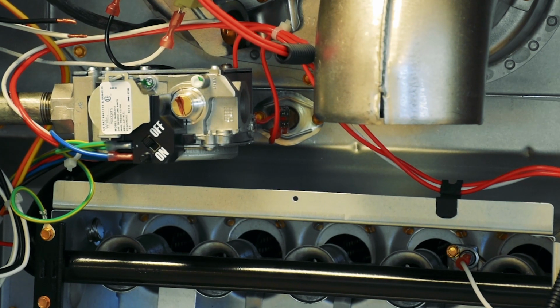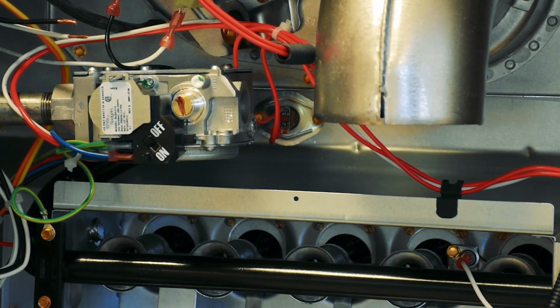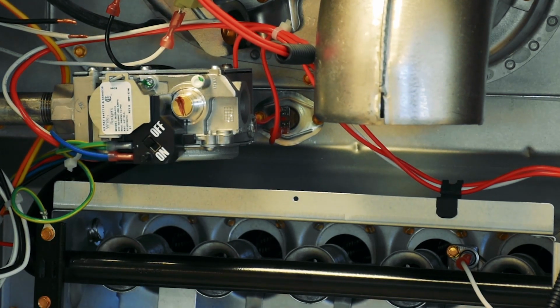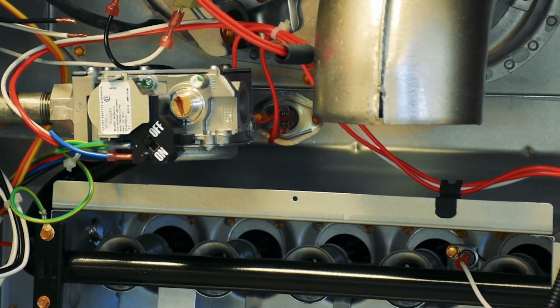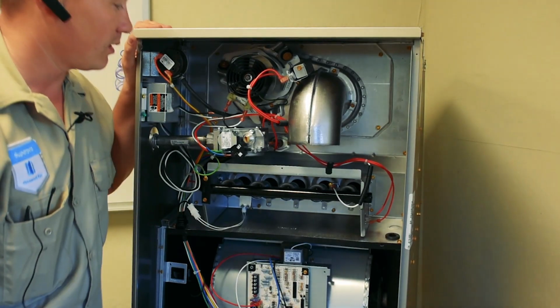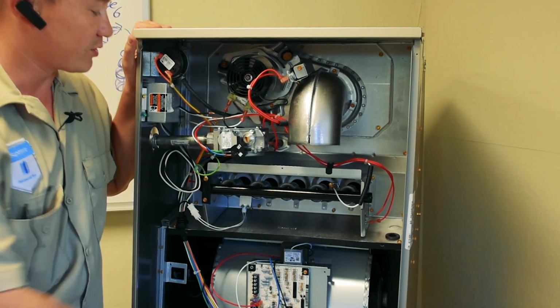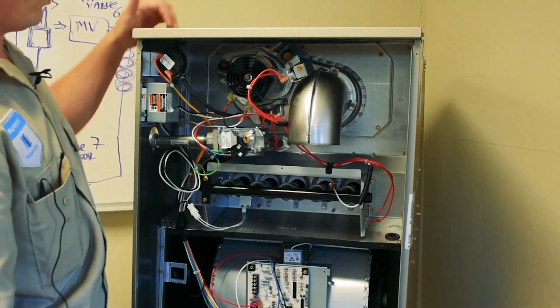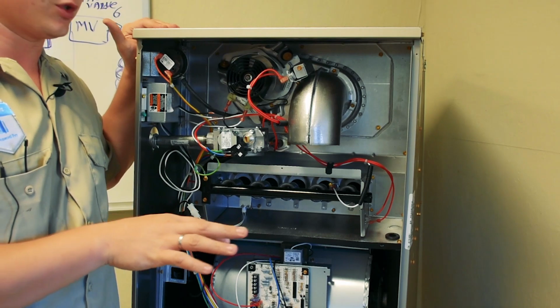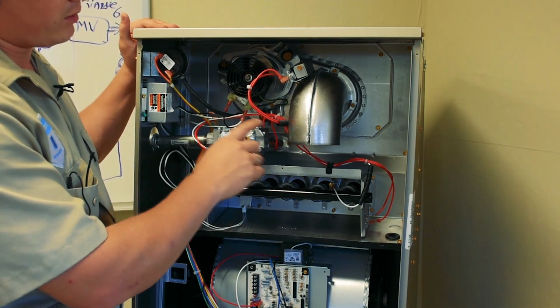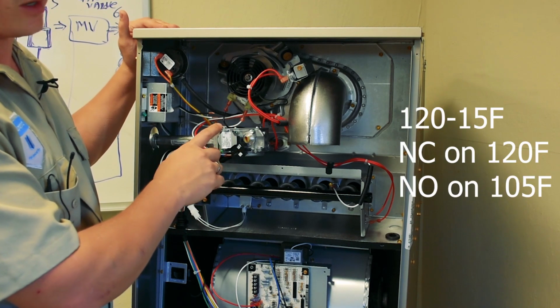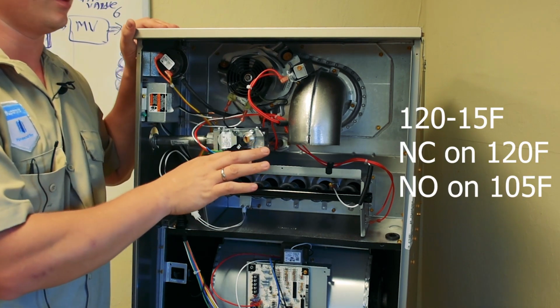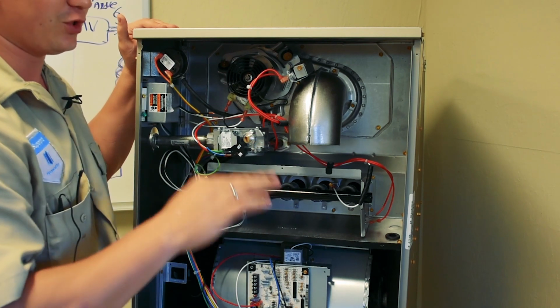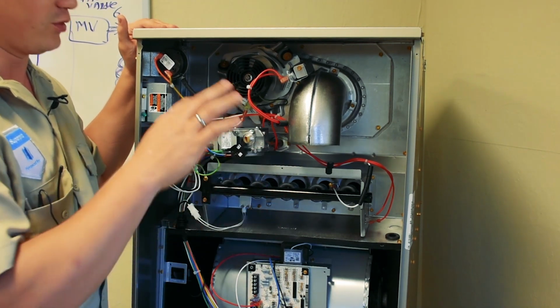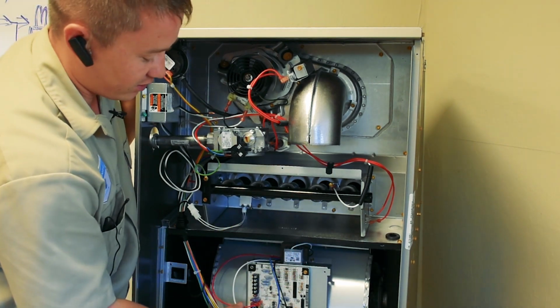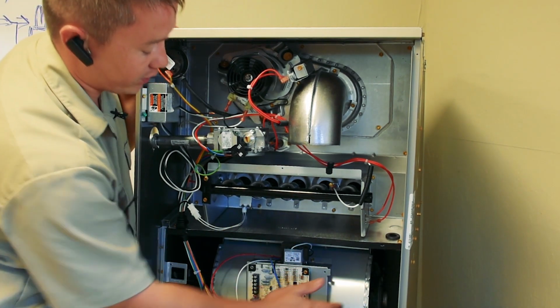After that, the air handler, the blower wheel motor, is still running and removing the heat from the heat exchanger, because the heat exchanger is still hot. It will keep running the blower wheel motor because the high limit switch is still hot. Usually that high limit switch has a setting of 120 minus 15 Fahrenheit. That means when the high limit switch reaches 105 Fahrenheit, it will turn off the relay on the control board which is running the blower wheel motor. That's it.